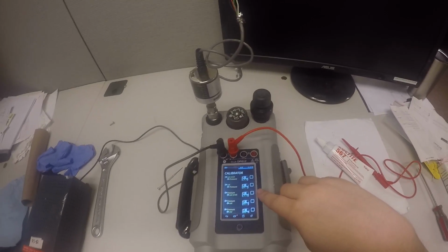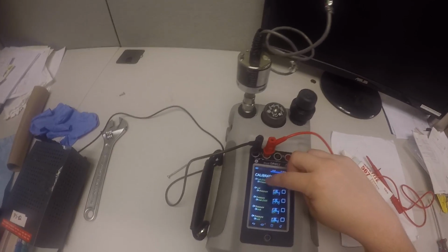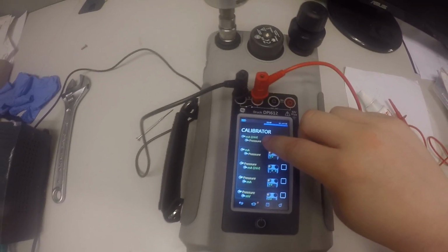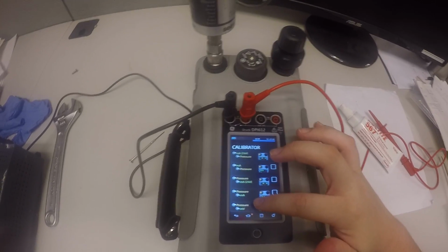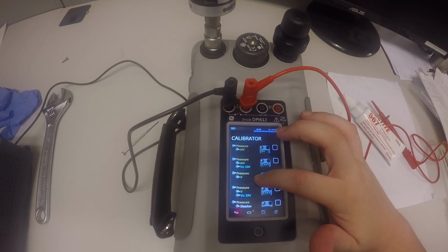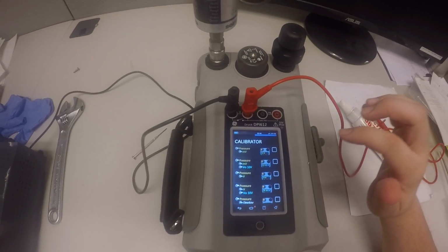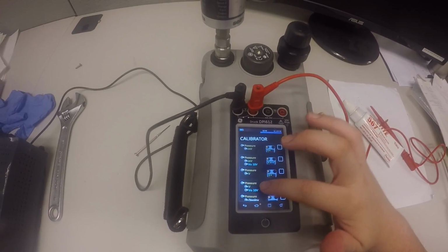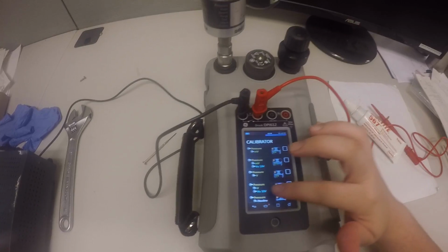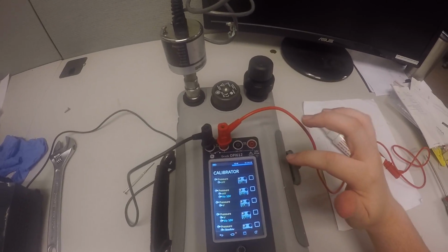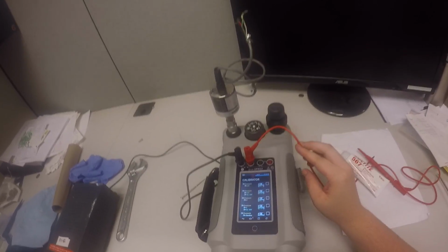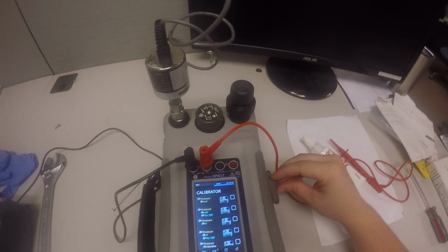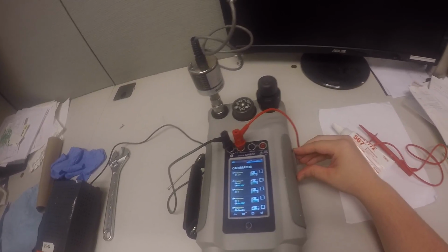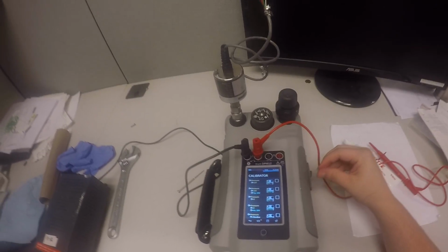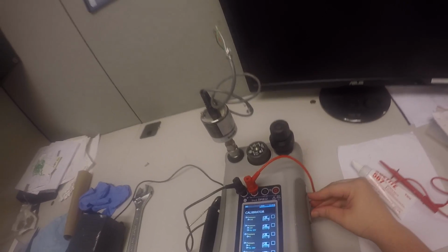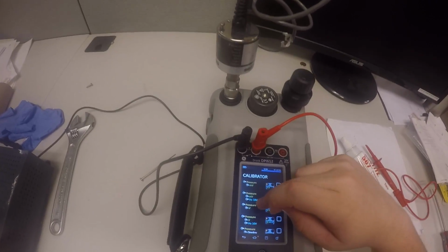Now if your pressure transducer has an output in milliamps, you're going to hit this first one, which is milliamps 24 volts. But if your pressure transducer is a voltage output, then you need to scroll down more. So there's two choices for voltage. You can either have volt just by itself, or volts, volt output 10 volts. So the volt output 10 volts selection is for when you're using the Druck output to power your transducer. You can only do this when your transducer takes excitation voltage of lower or equal to 10 volts. In this case, this transducer has an excitation voltage above that, so we're going to use just pressure volts.